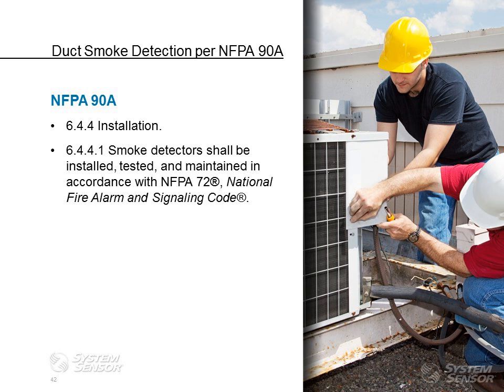Now, on NFPA 90A, we talk about their installation requirements. It states that smoke detectors shall be installed, tested, and maintained in accordance with NFPA 72, which is the National Fire Alarm and Signaling Code. That's important to know because that's what's going to determine where it gets installed, how frequently, and how it gets tested, and how it gets maintained. This is for NFPA 90A.